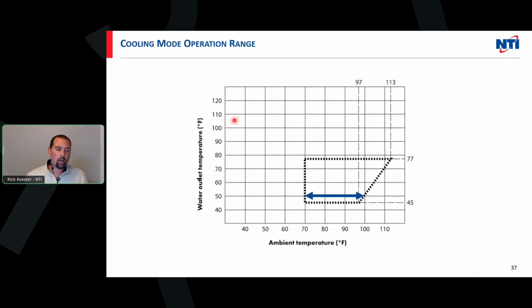Same thing on the cooling side, right? So if I needed 45-degree water, 45-degree water is going to get me to about 97 degrees outside, right? Typically we see about 48, 50 degrees, somewhere around there. Some applications maybe a little bit higher, depending on the moisture removal and everything else and the design of that air handler that we may be doing.